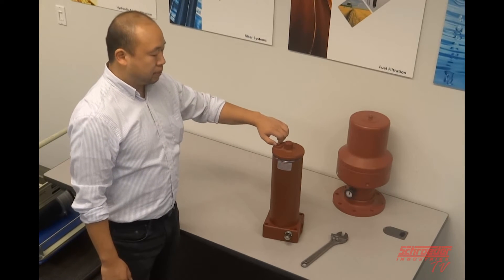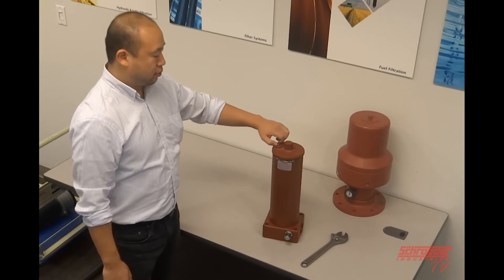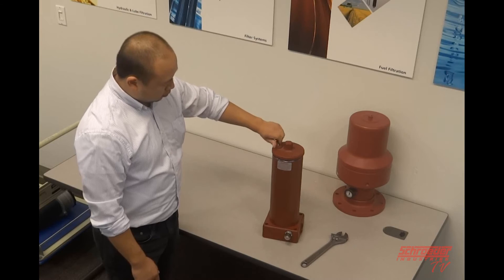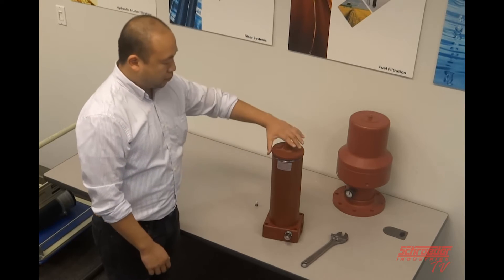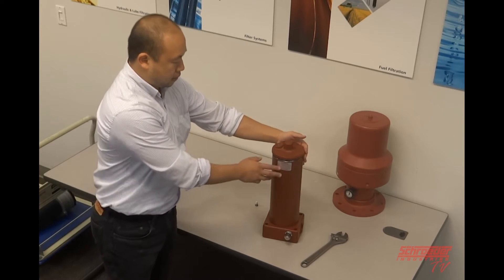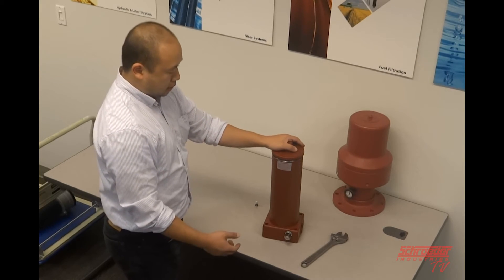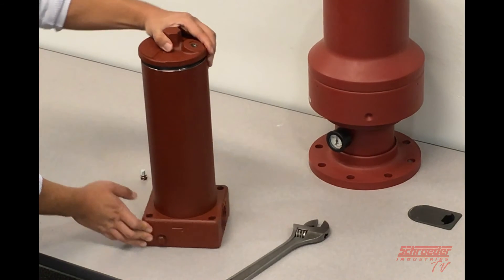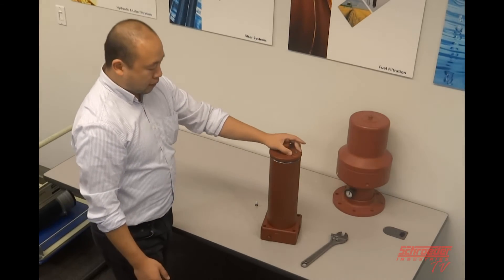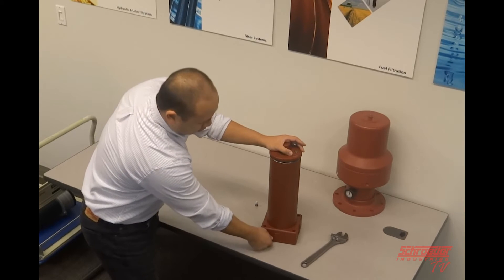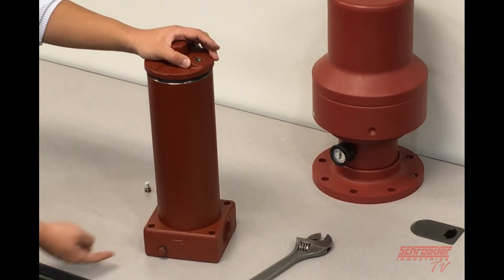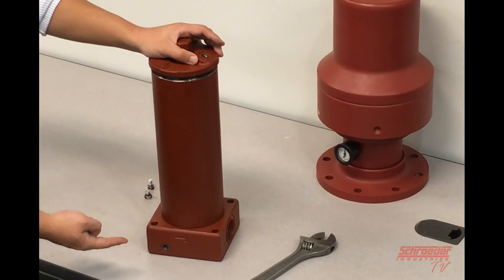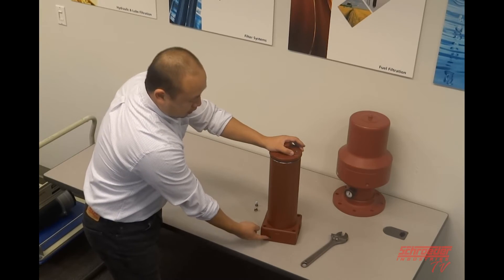So first, we will take the bleed plug in the cap to help alleviate the pressure in the housing. So that will help the pressure internally release before we change the filter itself. And we want to actually, even though it's a base ported filter, we still want to drain the fluid before we change the element. So we'll remove the drain plug in the cap here. And the fluid will drain out from here. And once fluid stops coming out, we can use a torque wrench.